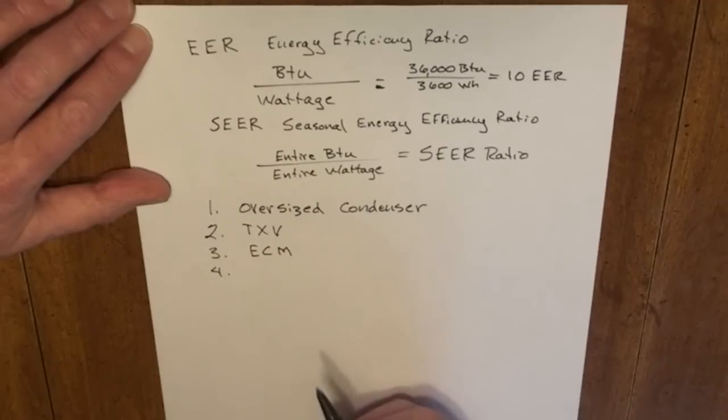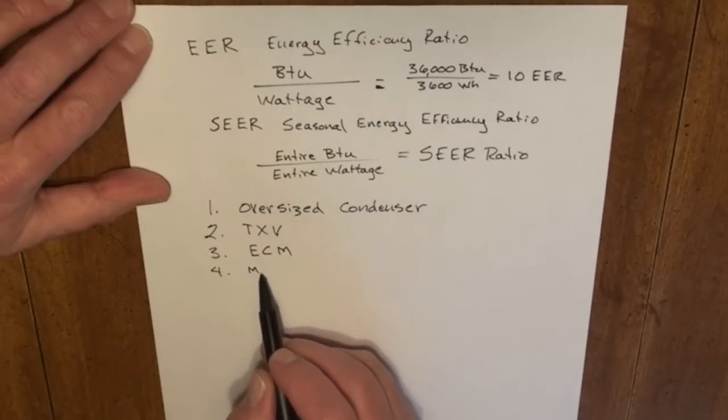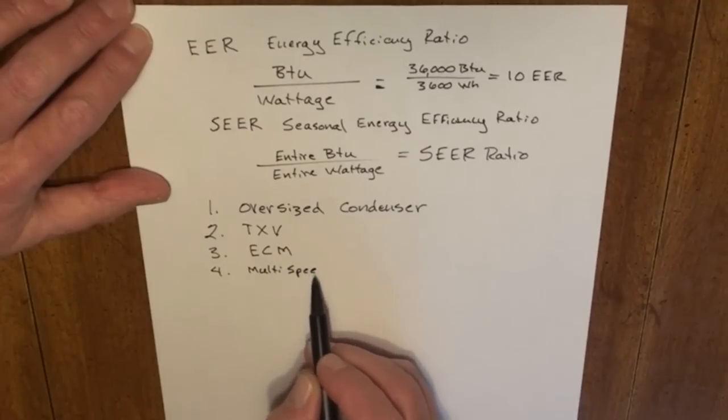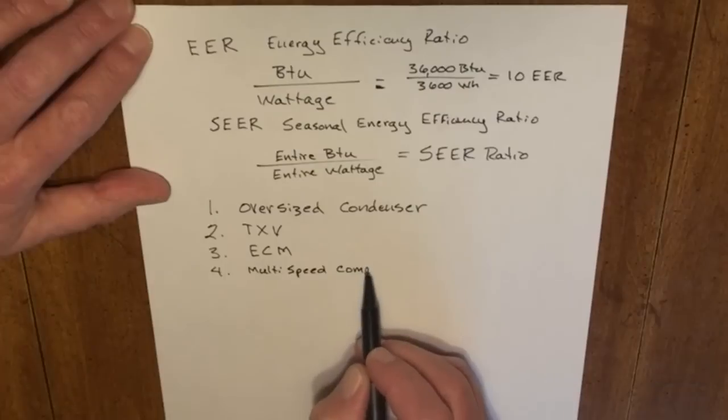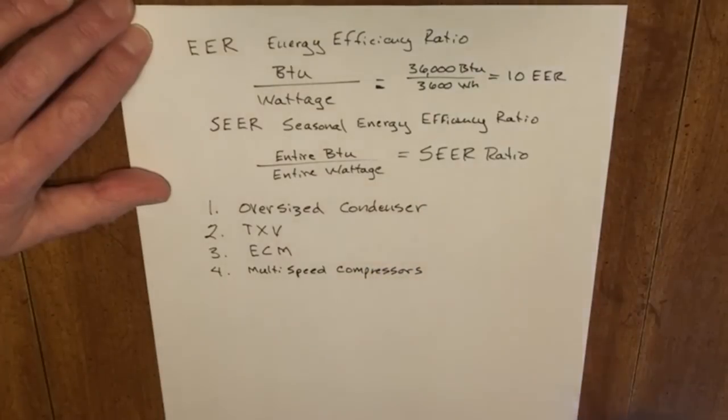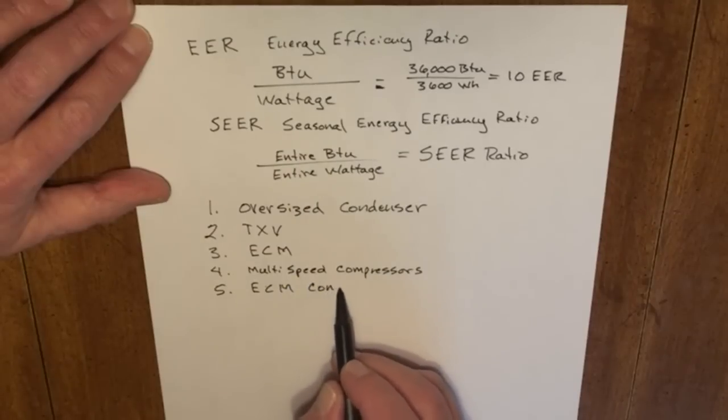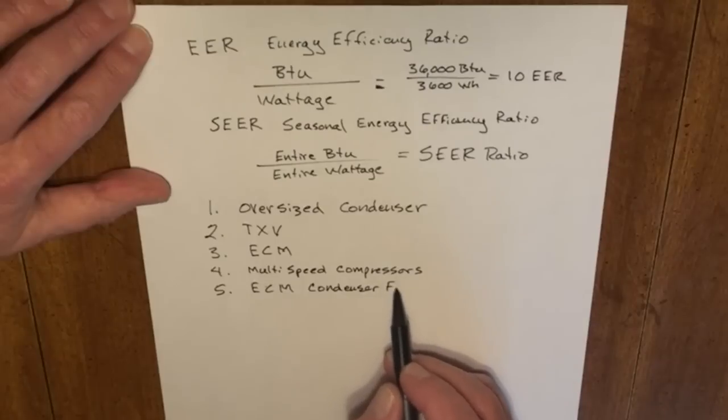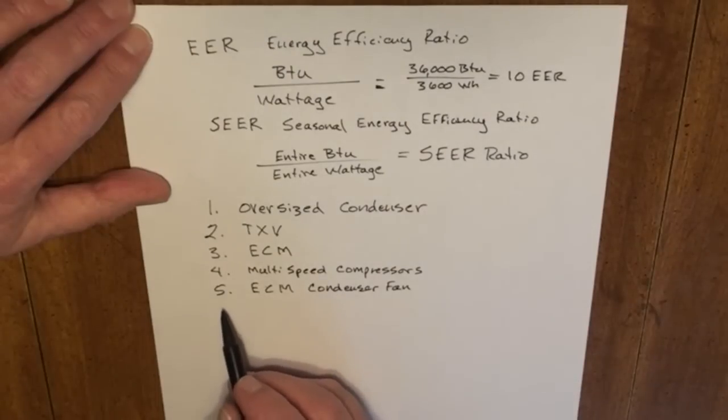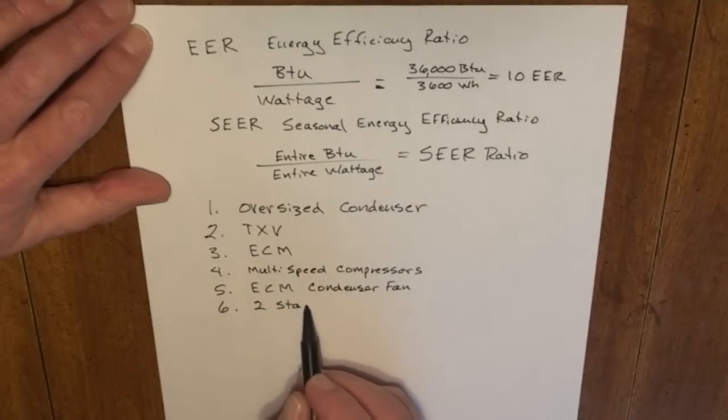Another item that can be used to increase energy efficiency are multi-speed compressors. No need to move more refrigerant than necessary. The multi-speed compressors can adjust their speed and amp draw in accordance with the needs of the structure. Electronically controlled motors for our condenser fans. Another possibility is to use a two-stage compressor.